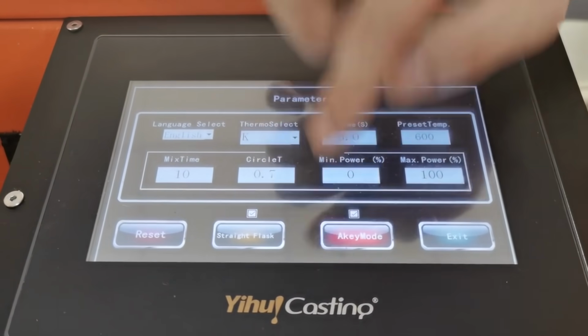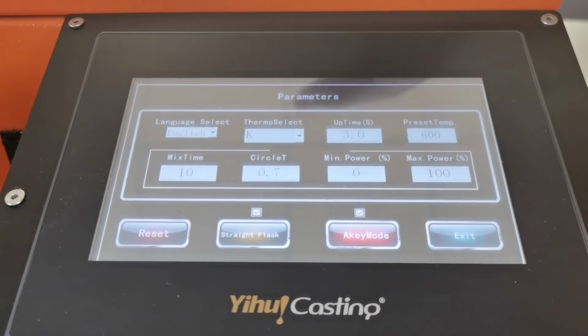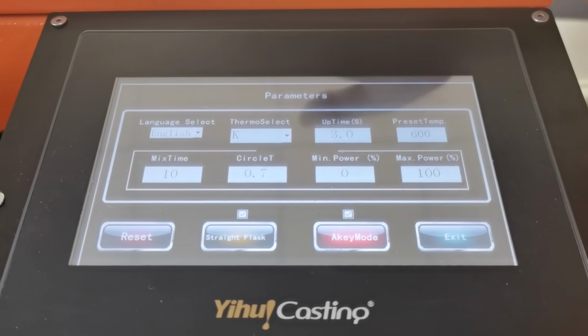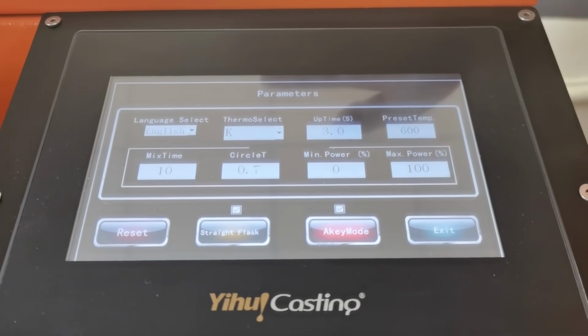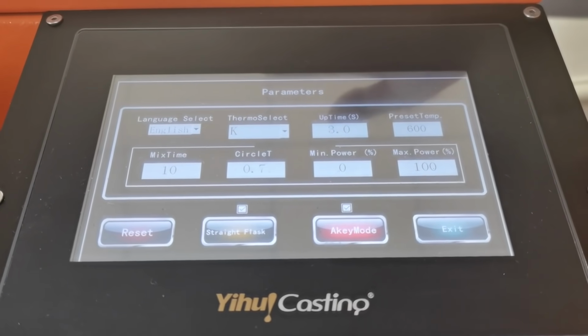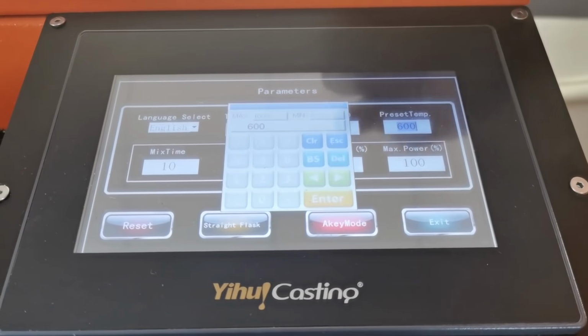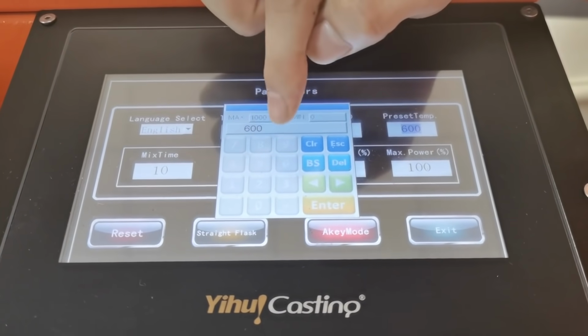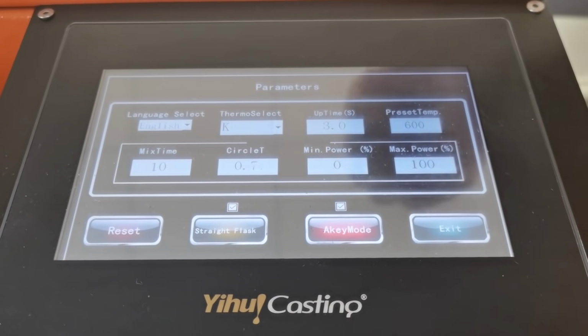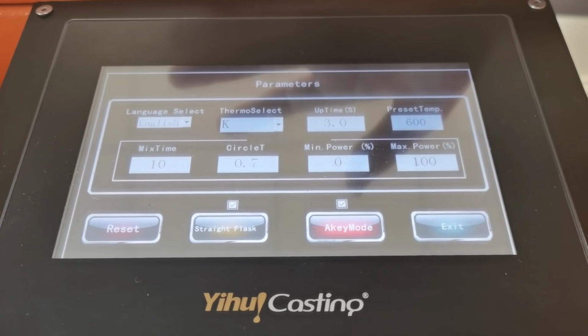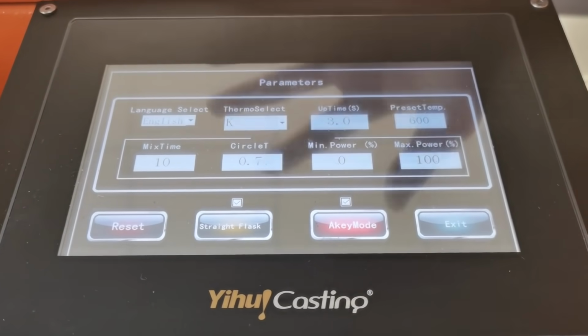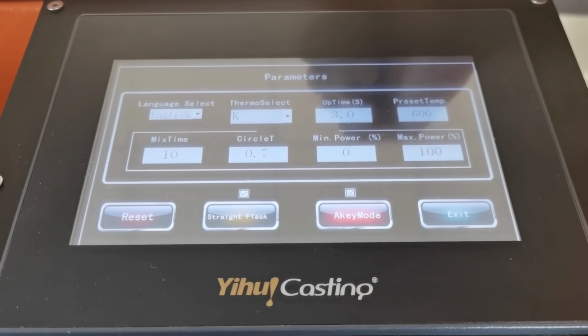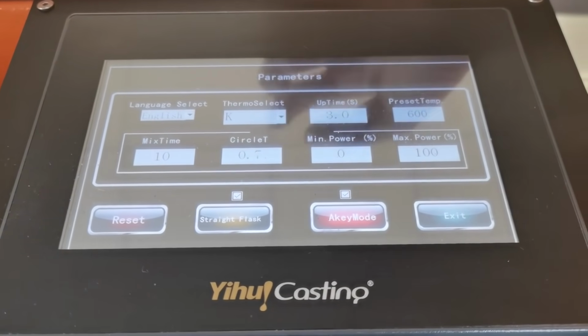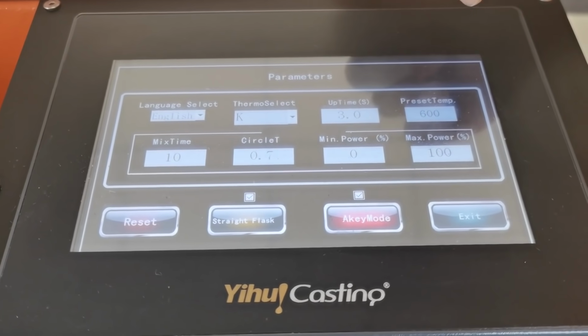For the uptime, we set 3 seconds. It means when the up cover and the down chamber turn to the right position, the system will close automatically after 3 seconds. Then turn to the preset temperature. For this part, we set 600 degrees. Actually, we can set a maximum of 800 degrees, but the higher the temperature you set, the faster the crucible will oxidize. So we recommend you set 600 degrees.